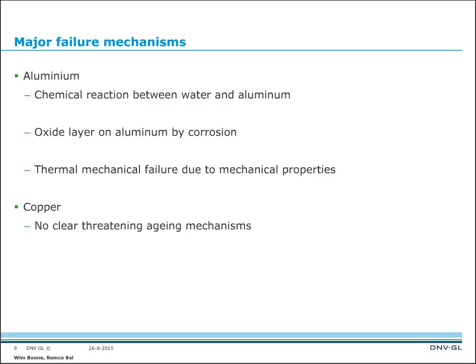The second mechanism is the oxide layer on aluminum caused by corrosion. Aluminum is far more sensitive to corrosion than copper, and this gives a complication when you have an insulated layer in your system instead of a conductive one.